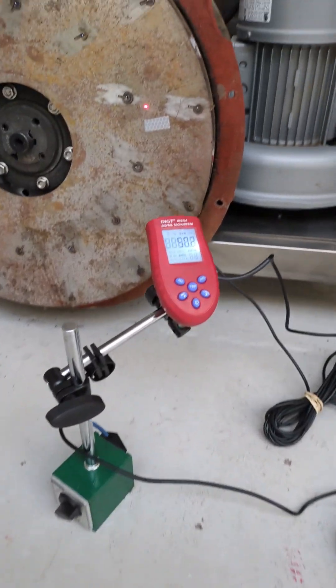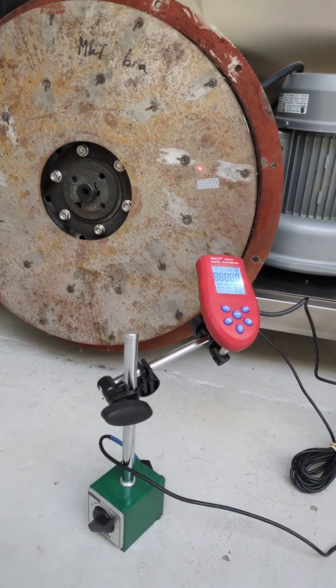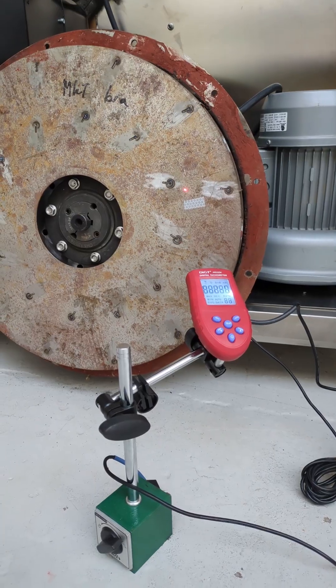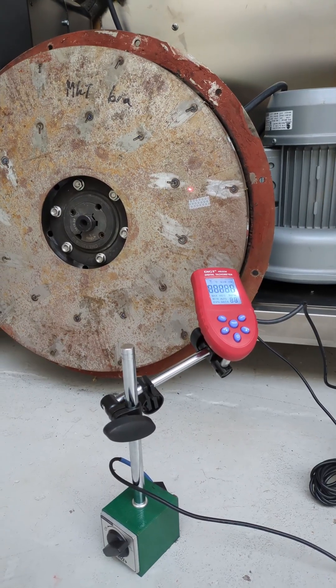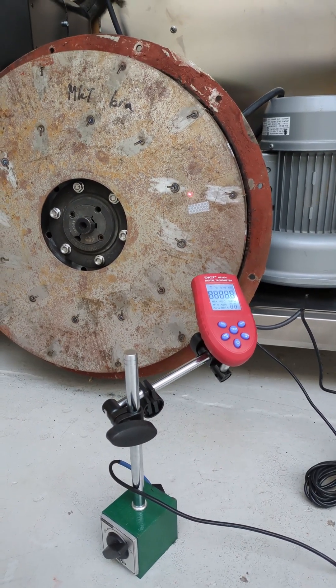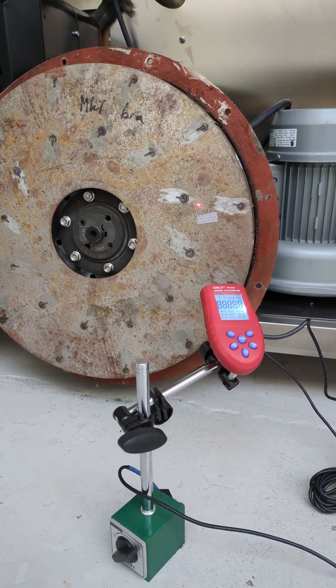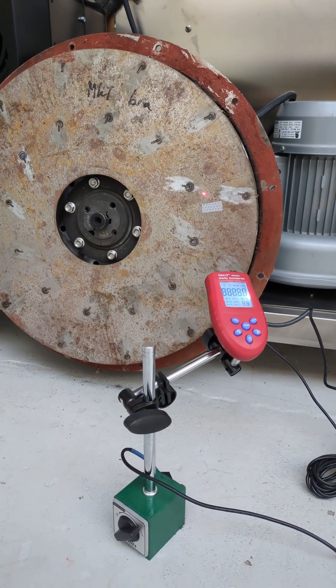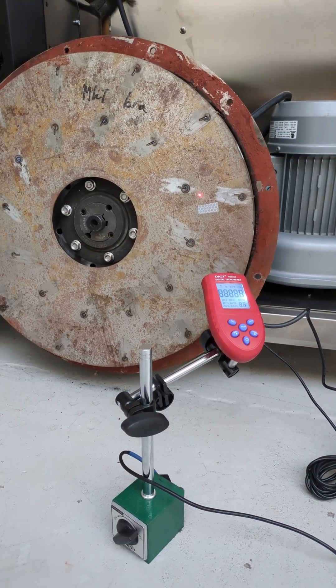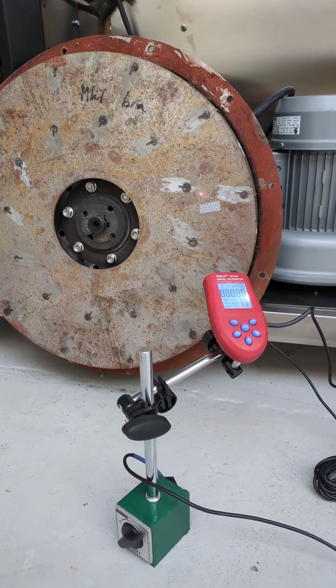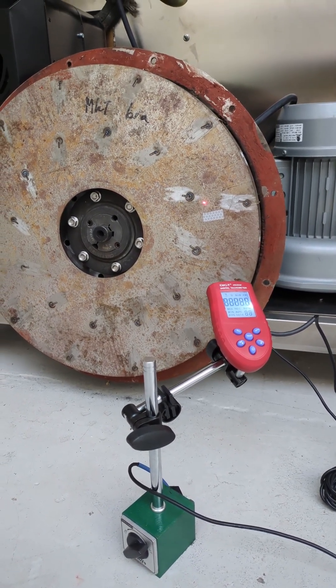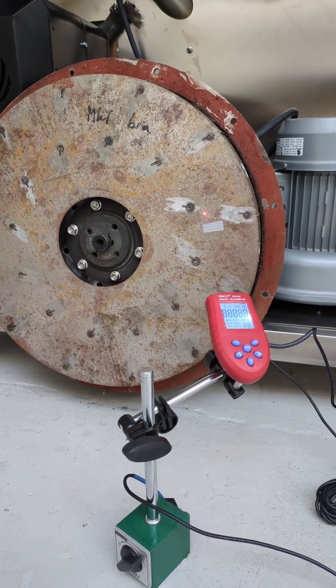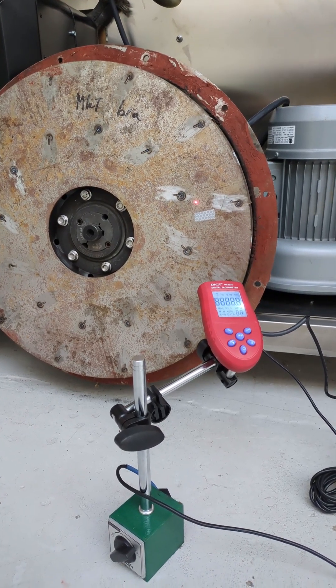Note that the tachometer is positioned at an angle to the reflective tape. That's because other scratches on the fan wheel will give signals back which creates error. So this is a safe way to do it.